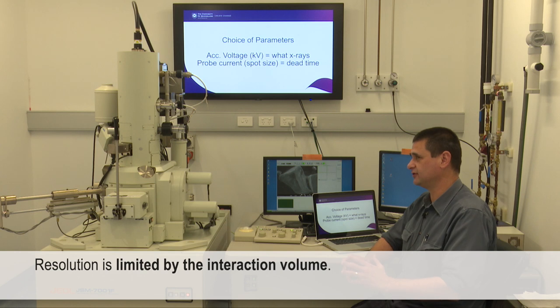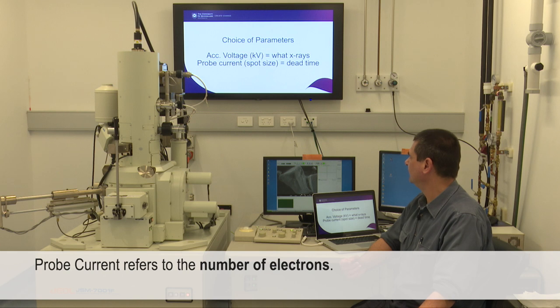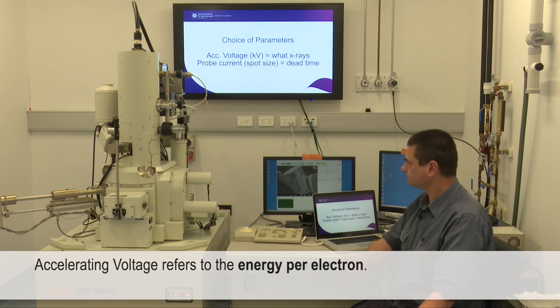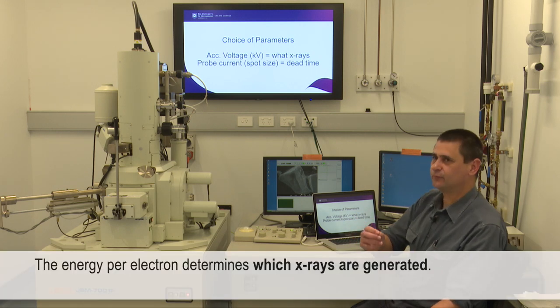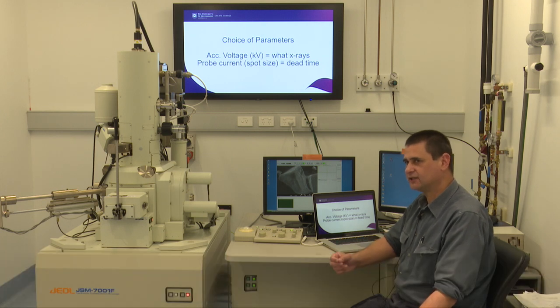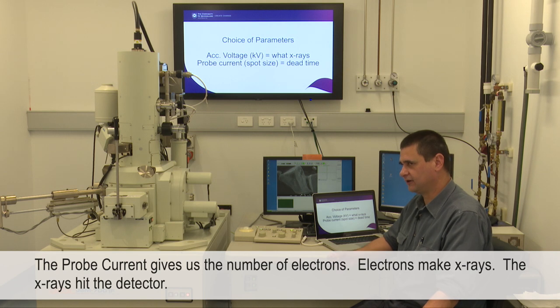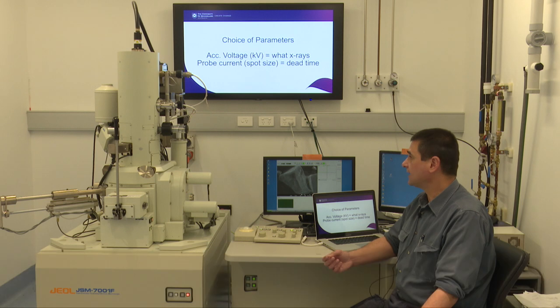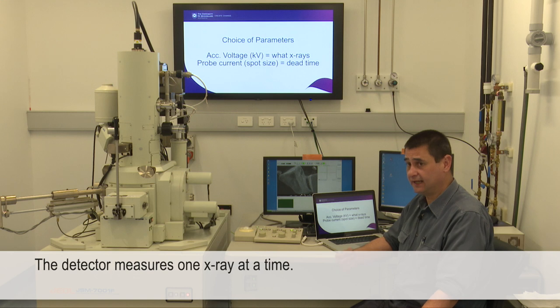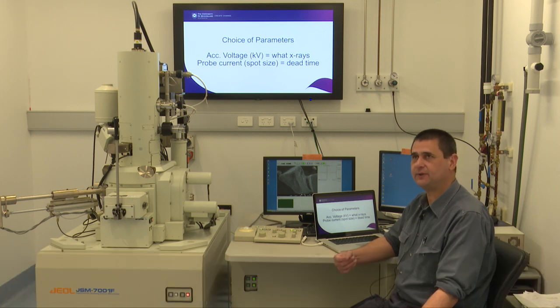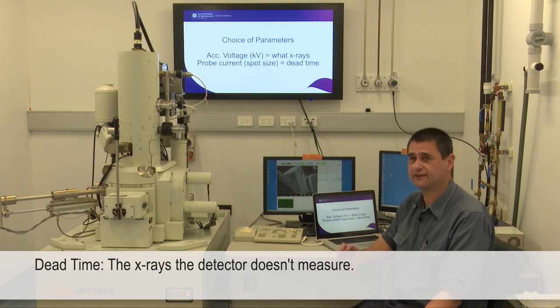The two very important parameters are the accelerating voltage and the probe current - often called the spot size. We're not so worried about resolution since we're limited by the interaction volume. The energy per electron tells us which X-rays we can generate - we can't generate X-rays above the electron's energy. The probe current gives us the number of electrons. The detector can only deal with a certain number of X-rays - it likes to measure one at a time - and if given too many it struggles. This is referred to as dead time.